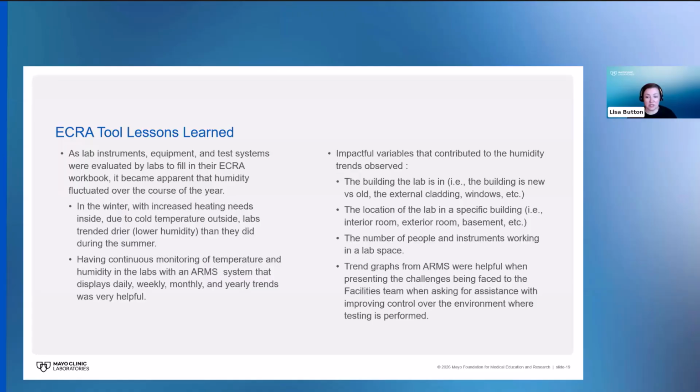And having that continuous monitoring of these environmental conditions within the labs really helped us understand where we might be at risk for going outside of the thresholds that were set by the manufacturers.